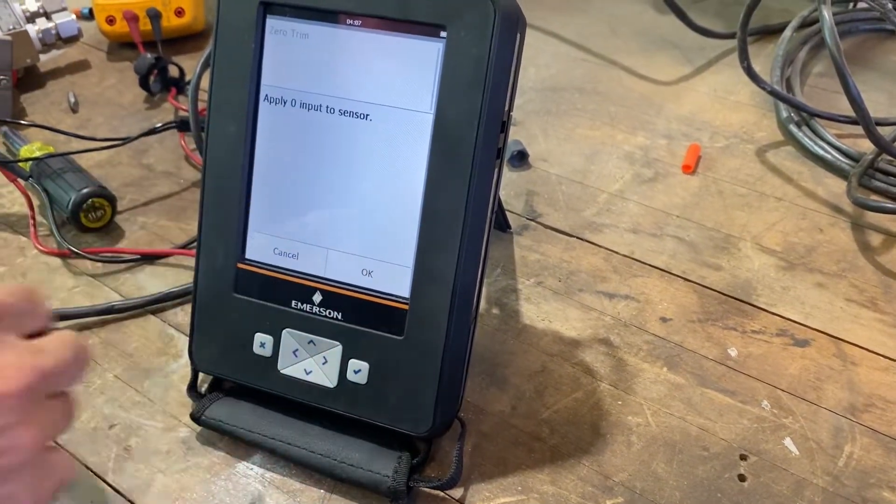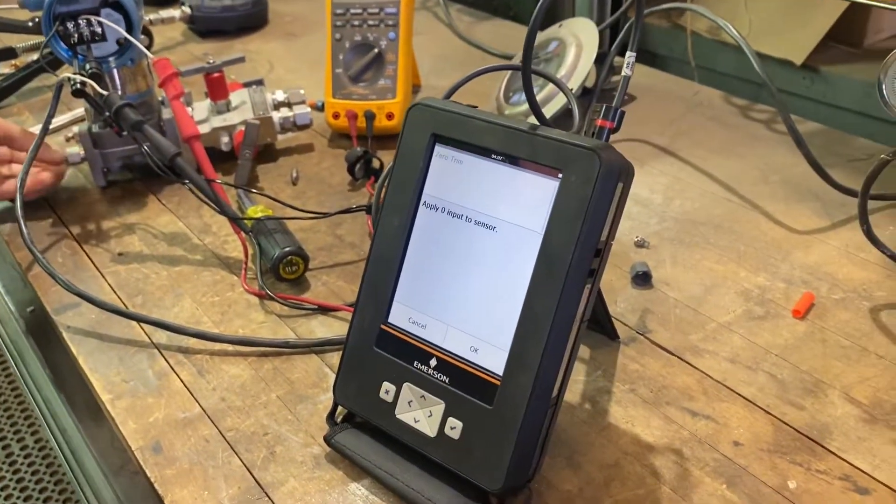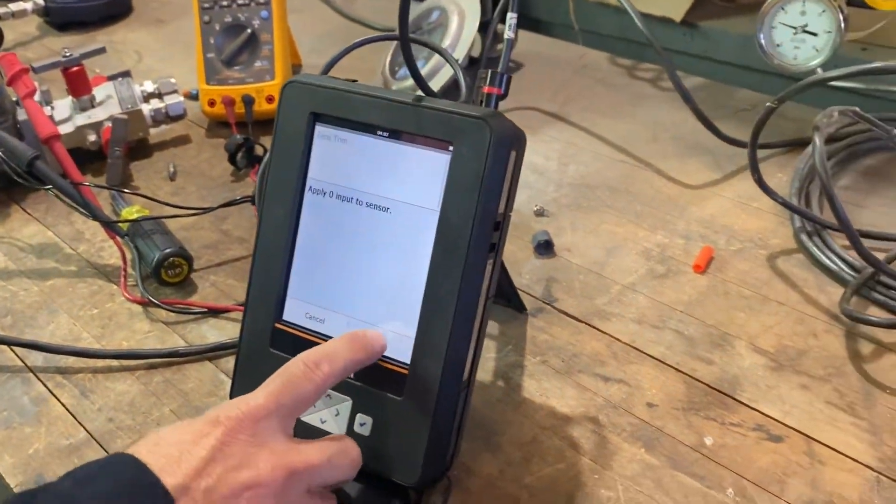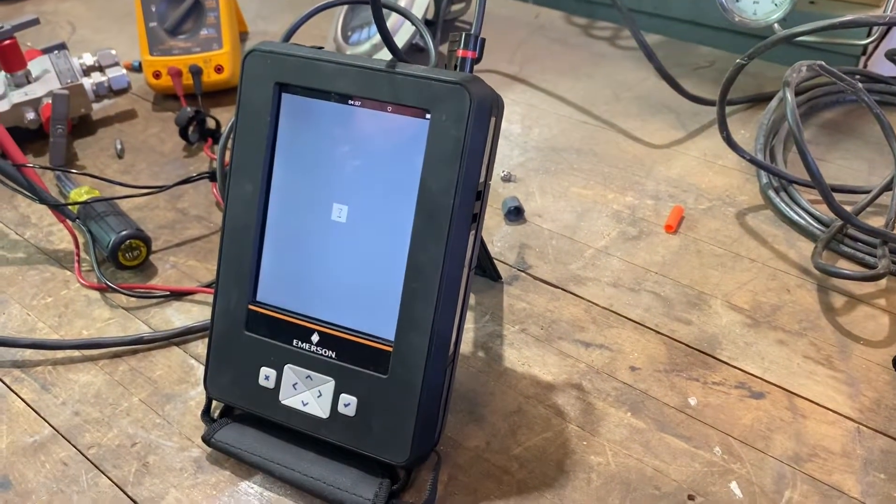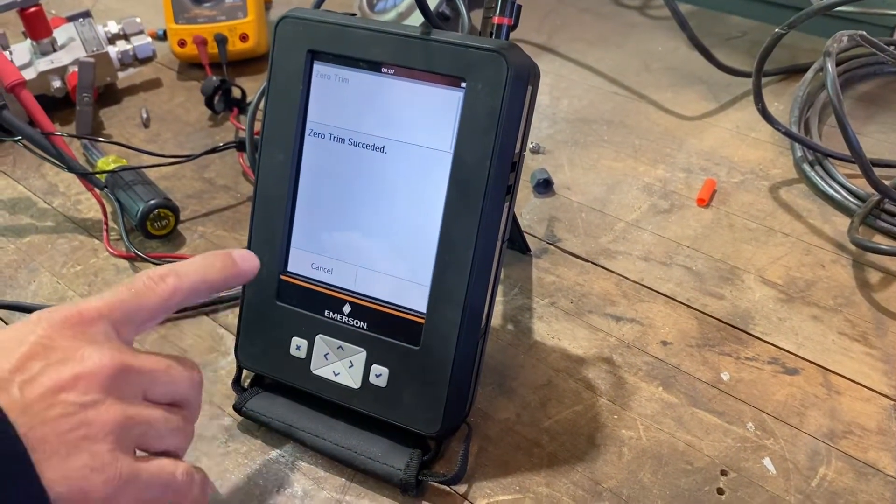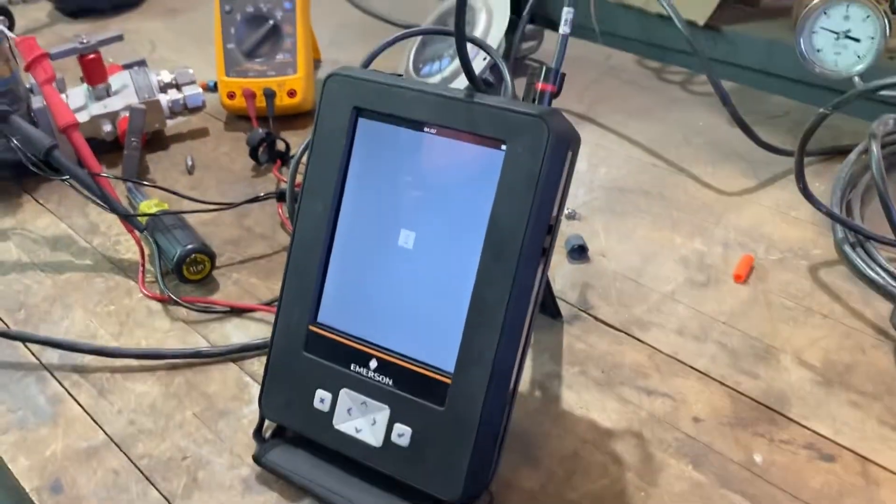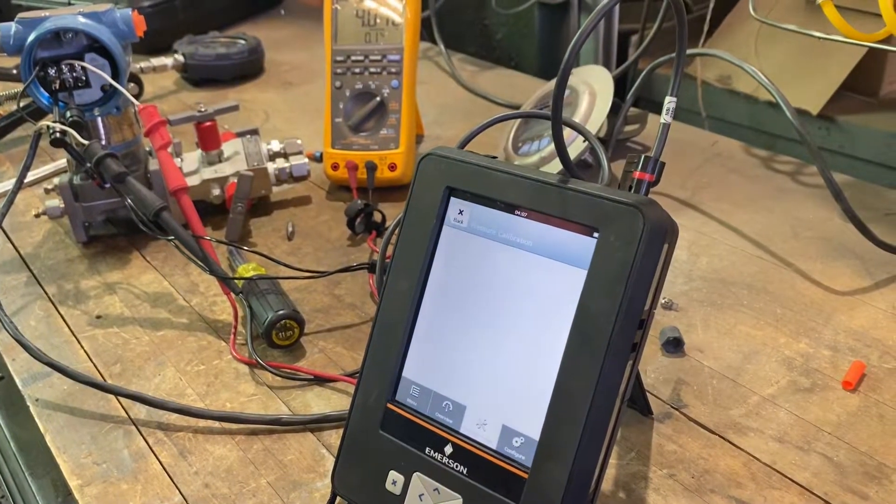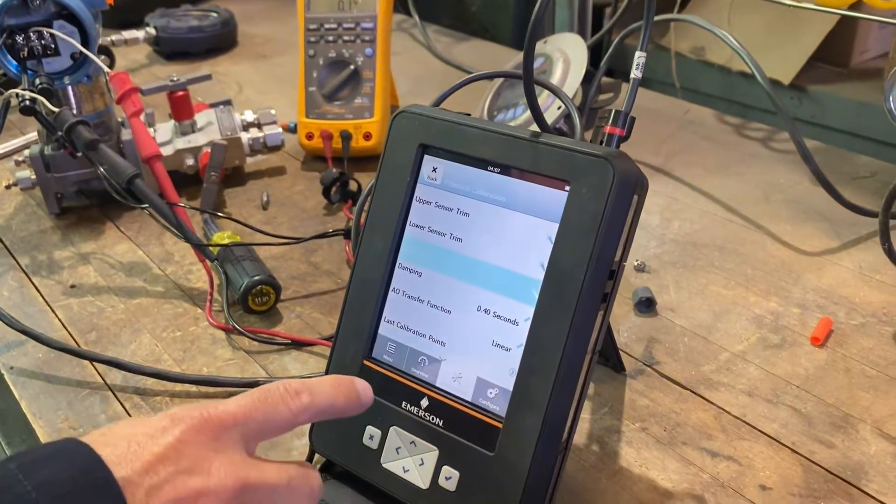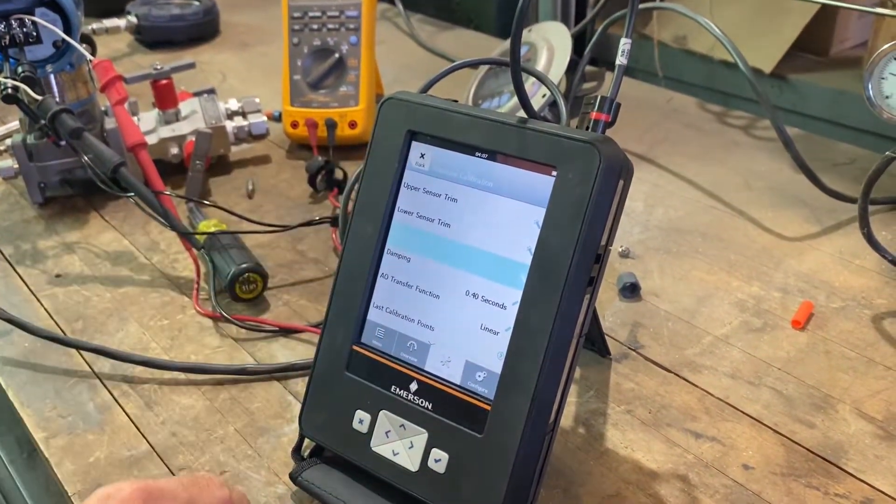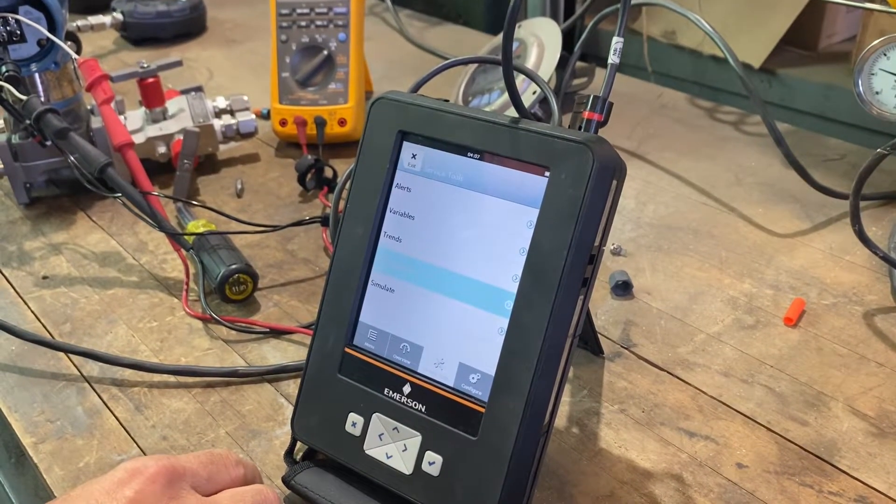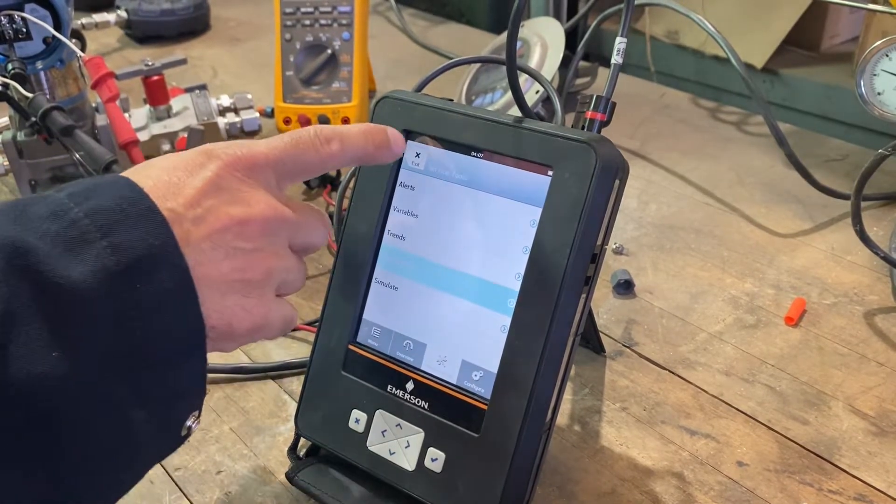Apply zero. We have it zeroed. You can't do this with any pressure on it. These plugs are open. You hit okay. Zero trim successful. Okay. And that's how you zero it.